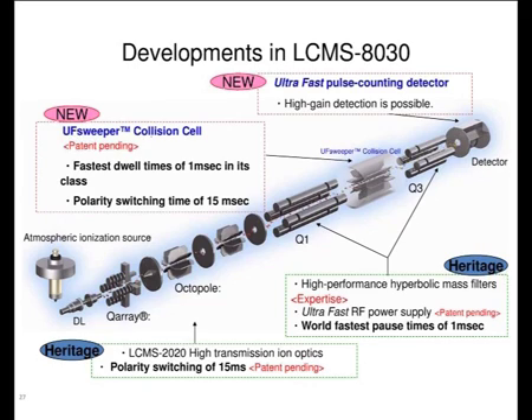This is the inside of the triple quadrupole. This is the interface. We can use ESI or APCI. This is the DL, the desolvation line. You can set the temperature for the desolvation line so that it removes the solvent associated with the molecules. The ions enter the Q array and the octopoles. These act as ion guides that focus the ions in the same direction, and then these are the skimmers. The skimmers are used to maintain the vacuum difference. The ions enter the quadrupoles, where the selection of the ions takes place based on mass to charge ratio. Then this is the collision cell where the fragmentation takes place. In the third quadrupole the product ion gets scanned or detected, and there is a detector.